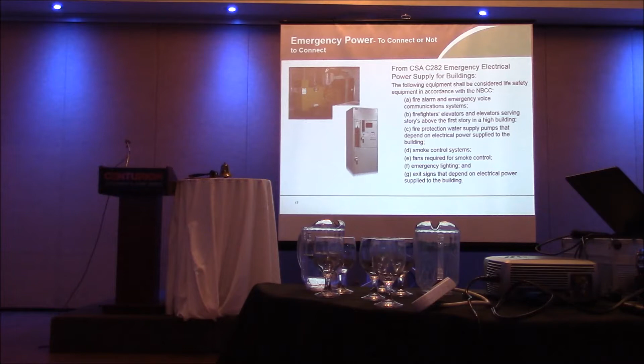That's it. I don't see chiller on there. I don't see domestic water booster pump. Now, I can supply them if my generator is large enough, but I have to be greedy. I have to put in a second transfer switch. It can be fed from the same generator, but it's a completely separate supply set up so that if that stuff we're supplying, the chiller, the domestic water booster pump, I don't know, the beer fridge in the building operator's room, whatever it is, if that load is in danger of taking my generator offline, it gets dumped. And we support the primary emergency loads first and foremost. They transfer first, they get first priority.